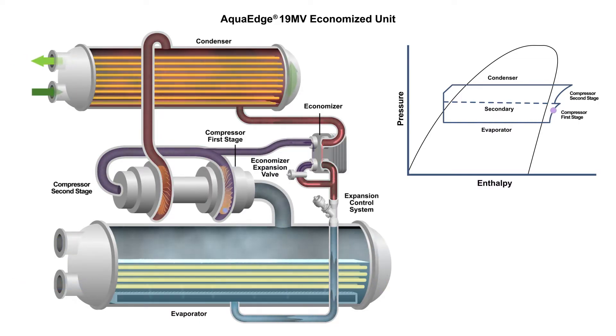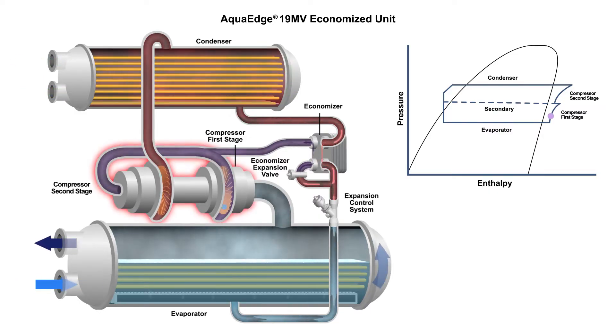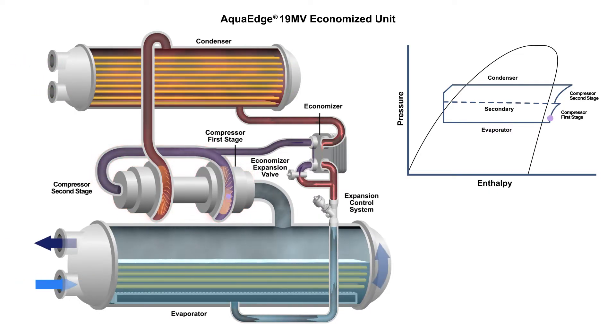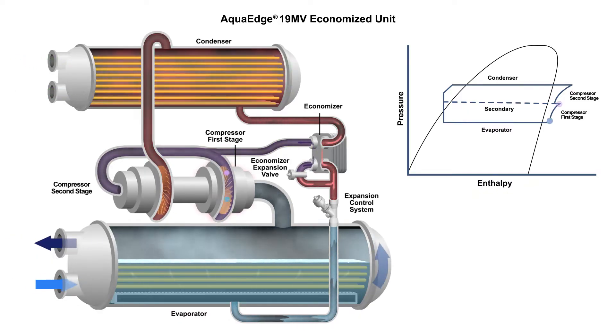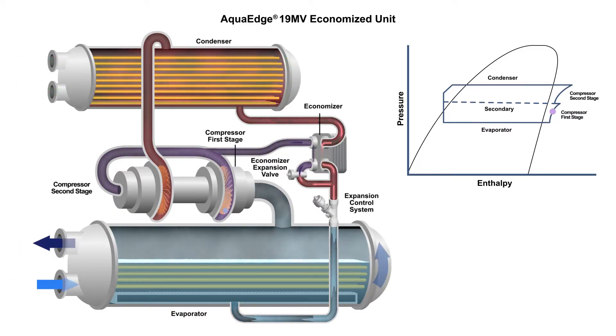The refrigerant vapor is now drawn from the evaporator into the 19MV's back-to-back two-stage compressor. Flow is controlled by the position of the first stage inlet guide vane, and the first stage impeller compresses the refrigerant vapor to an intermediate temperature and pressure.